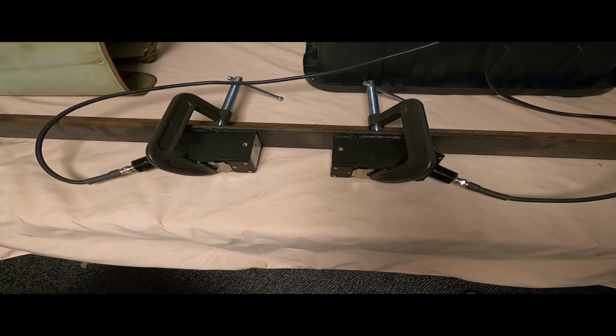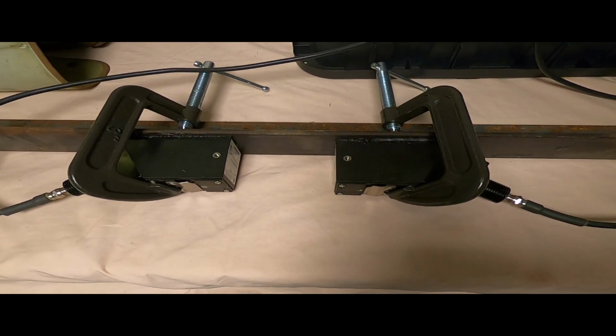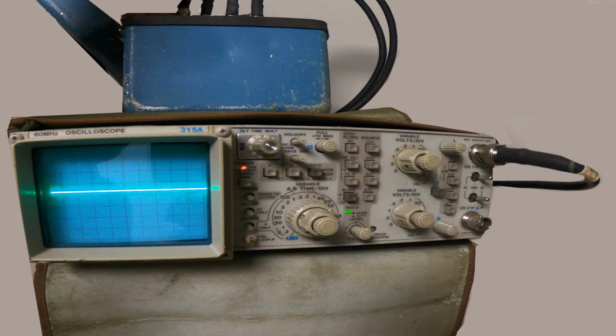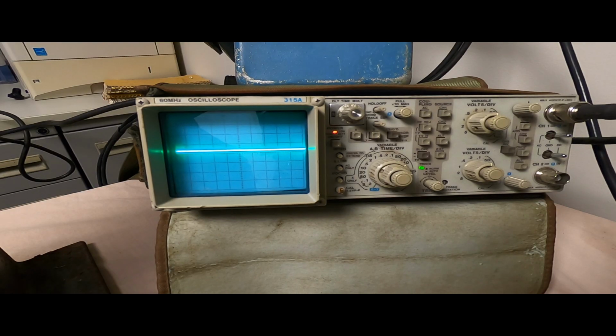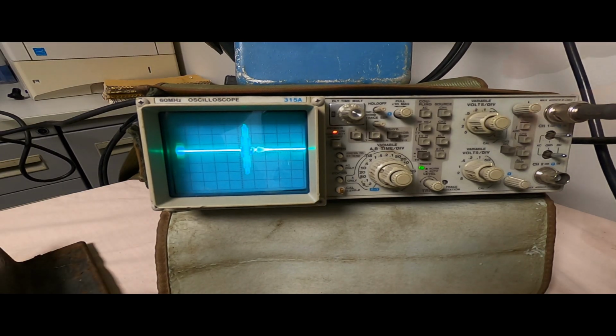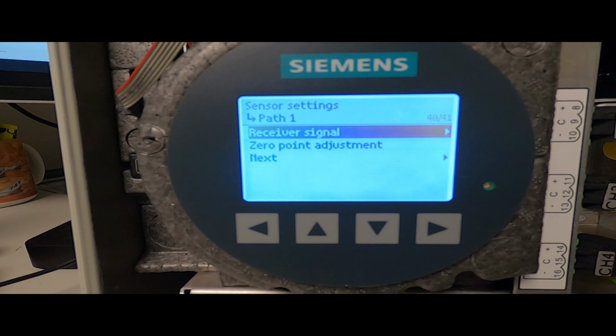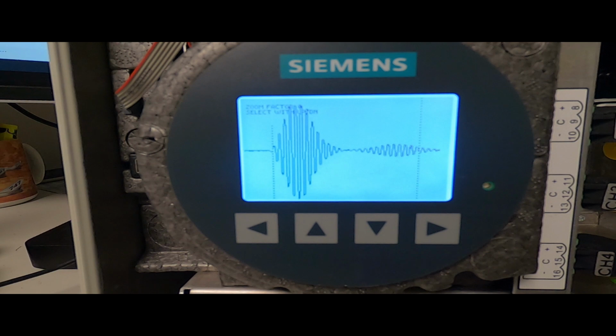To demonstrate this, I've clamped a pair of sensors to a piece of steel plate at the appropriate spacing for a 6-inch pipe. I'll use a transmitter and an oscilloscope to view the ultrasonic signal propagating in the steel plate. And there it is. Out in the field, your pipe wall will perform the same function as the steel plate. And with some creative programming, which is the whole point of this video, you can make the flow meter see the ultrasonic energy induced into the pipe wall, just as we did in the steel plate.